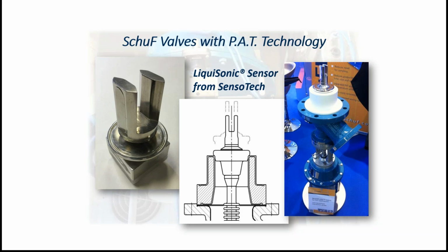As a salesman for the valves, I would try to push a customer that way, but it's easier on new equipment to put an additional nozzle into the tank. The only issue with these additional nozzles is sometimes it's limited by the length of the probe—it has to be a certain length, and the fiber optic cable connected to it can only be bent at a certain radius. So there are certain limitations. Yes, the biggest advantage is probably on existing reactors. On new reactors, customers have the chance to integrate the probe somewhere different, but that's where we see most of our business, in retrofits of existing equipment.